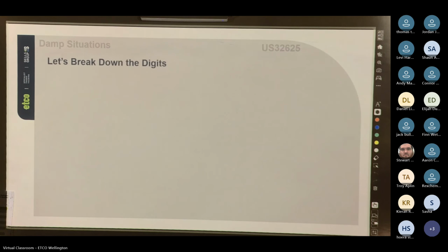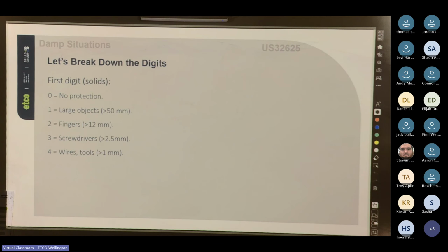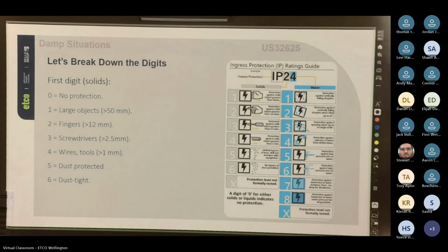Cool. So let's break down the digits. For the first digit, solids: 0 is no protection. 1 is large objects bigger than 50 millimeter diameter. 2 is fingers, more than 12 millimeter. 3 is screwdrivers, more than 2.5 millimeter. 4 is wires or tools, more than 1 millimeter. 5 is dust protected. 6 is dust tight. So from 0 to 6, they all have different meanings.